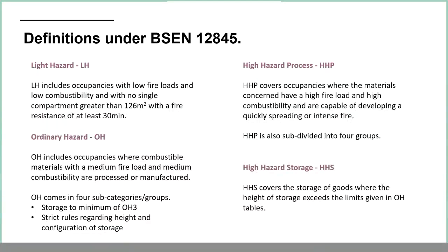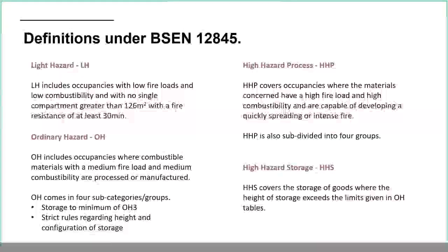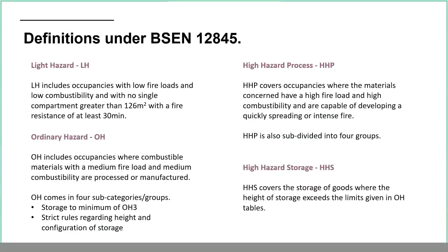Another important point: if you have any kind of storage at all, it should be ordinary hazard group three — that's the only ordinary hazard group which allows for some storage.